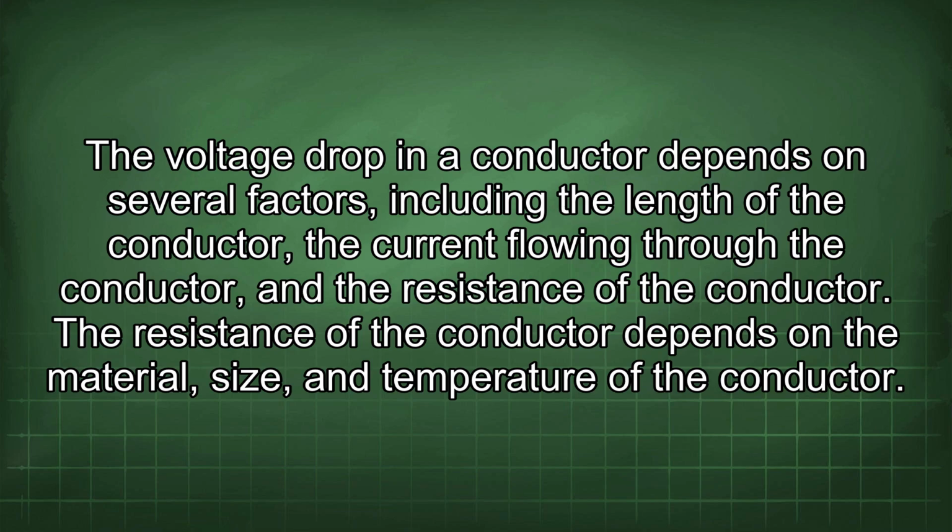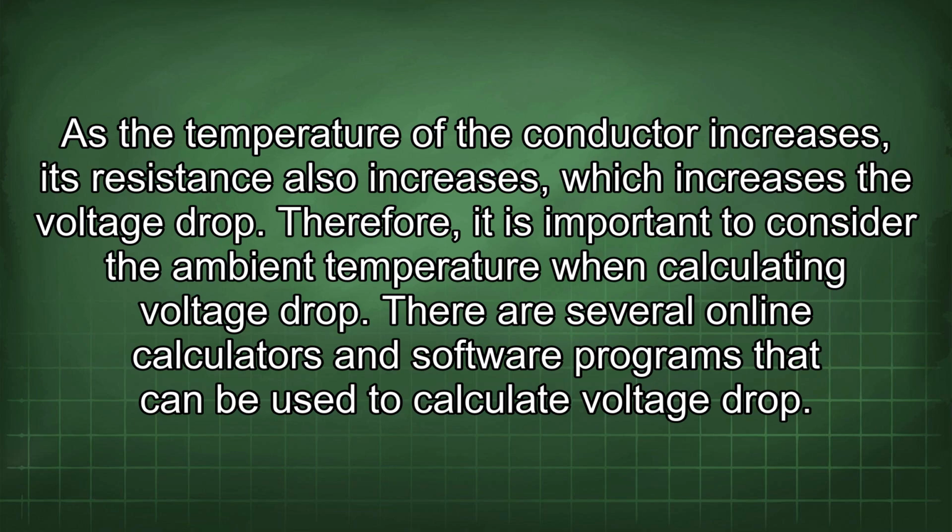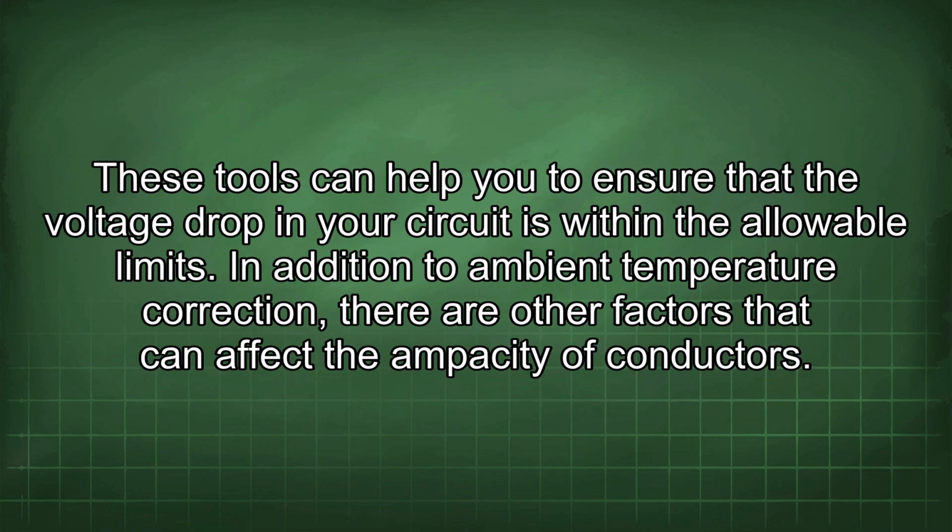The voltage drop in a conductor depends on several factors, including the length of the conductor, the current flowing through the conductor, and the resistance of the conductor. The resistance of the conductor depends on the material, size, and temperature of the conductor. As the temperature of the conductor increases, its resistance also increases, which increases the voltage drop. Therefore, it is important to consider the ambient temperature when calculating voltage drop. There are several online calculators and software programs that can be used to calculate voltage drop. These tools can help you to ensure that the voltage drop in your circuit is within the allowable limits.